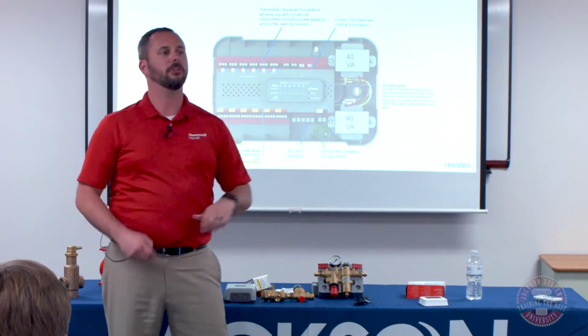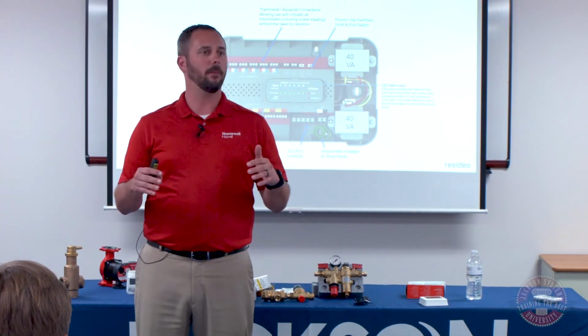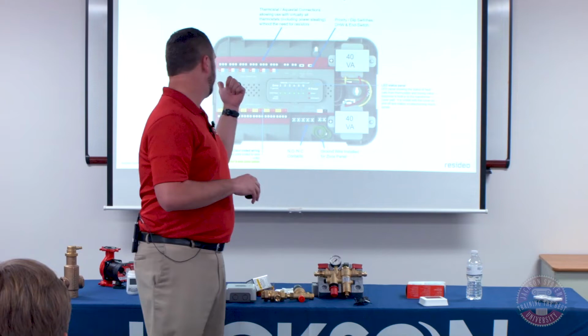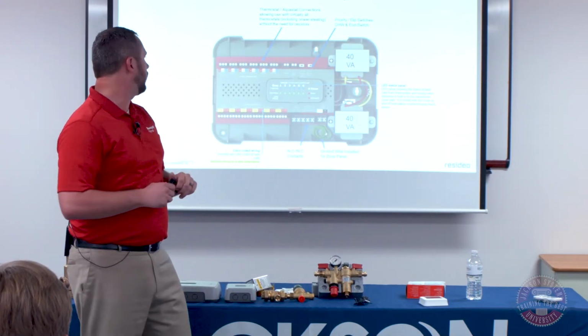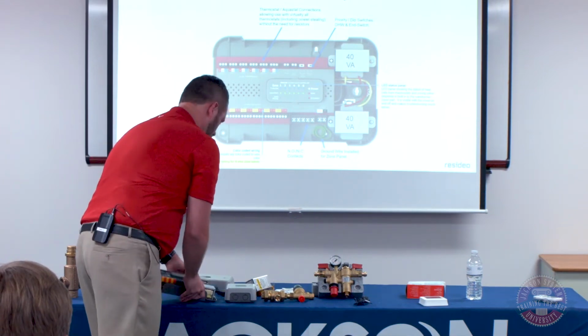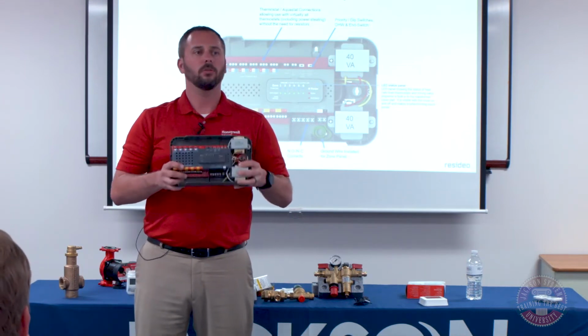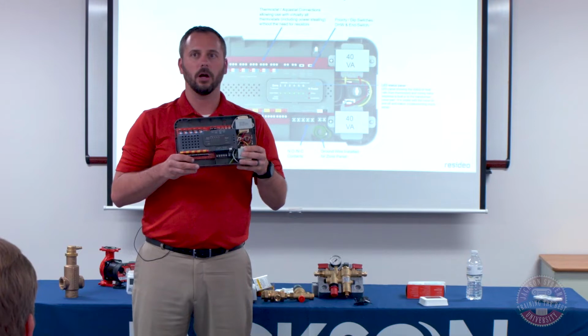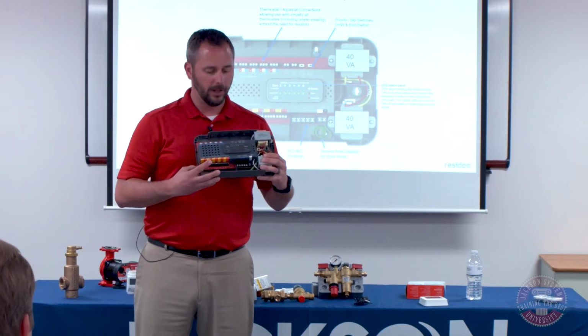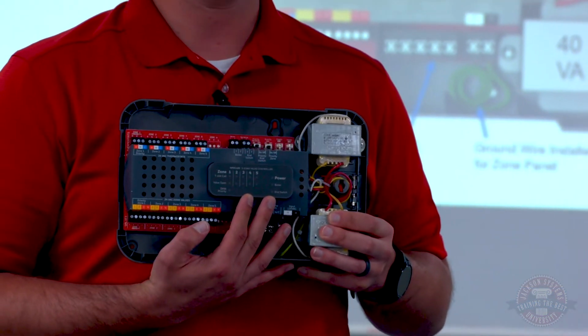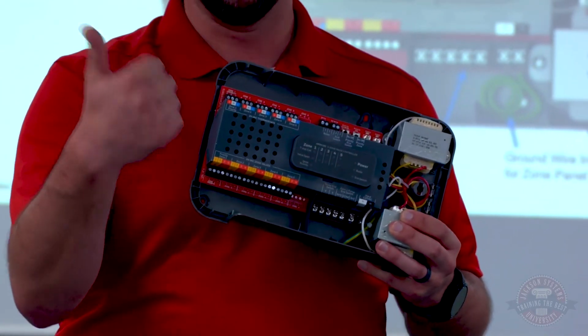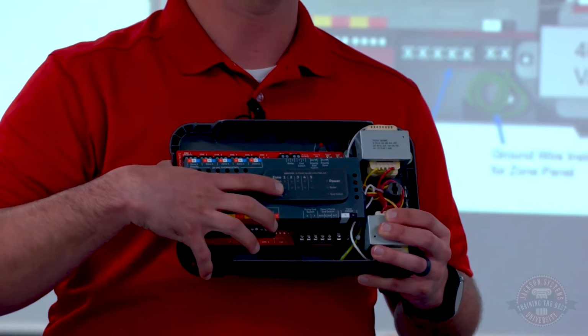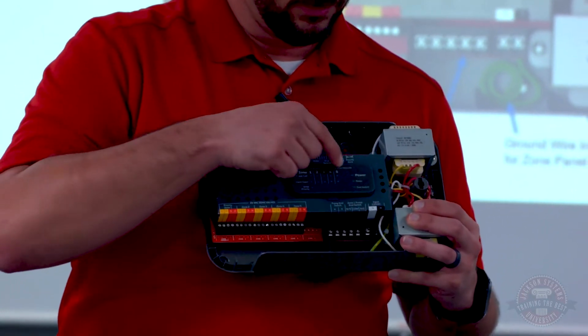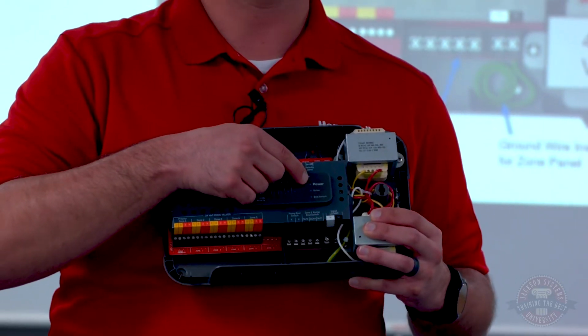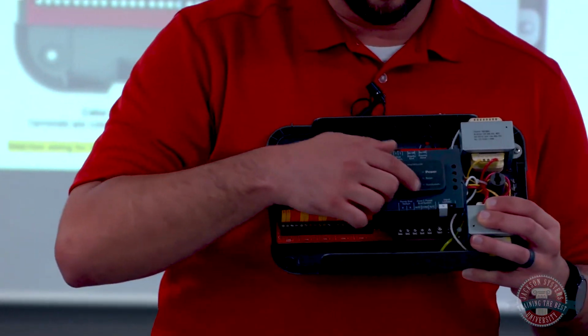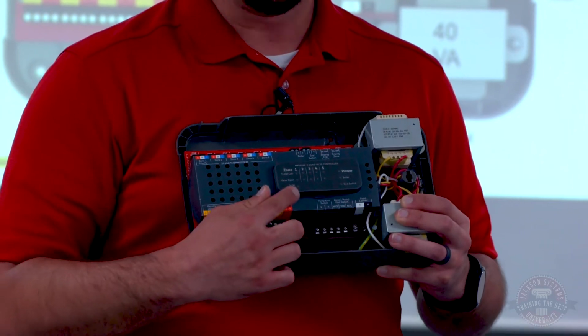So if we look at a cross-section here, here's essentially the guts. Now I'm showing the zone valve relay. For those of you that zone pump, I apologize, I don't have a cross-section on it in this presentation, but it's essentially the same principles. What we've got up across the very top, and I actually have one here with me, is what you hook everything to. Now the beauty of this is when I get the cover on, you saw the pictures I was just showing you where you saw wires going everywhere. What happens here is you've got LED diagnostic lights. It's going to show you what zone is calling for heat, what thermostat is calling for heat up across the top. Down at the bottom we have the zone valve that's calling for heat, or if the pump should be turned on. We have the all-inclusive, does the panel have power? So we have a power light on here. And then you've got a couple other LEDs on here. So you've got boiler, we have an extra in switch, and then priority.